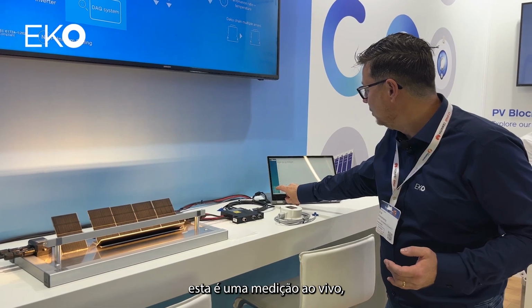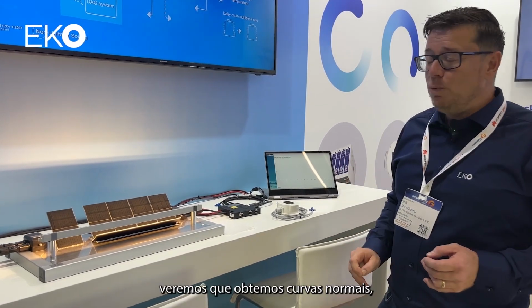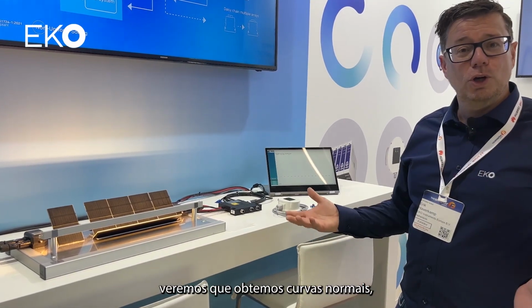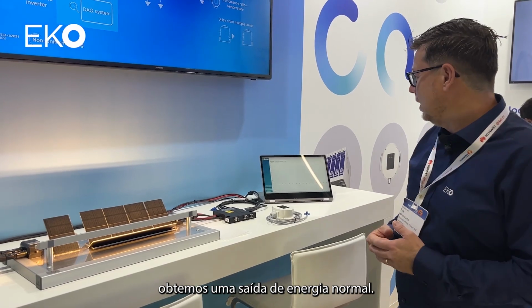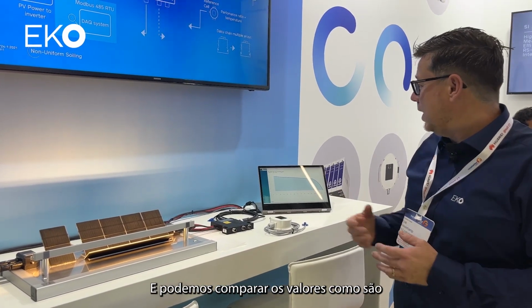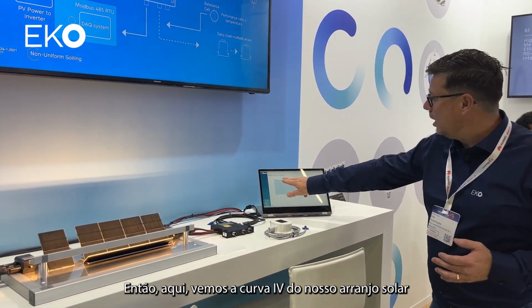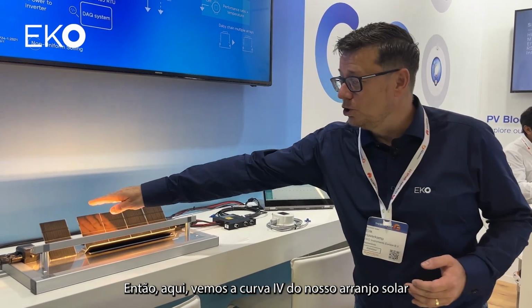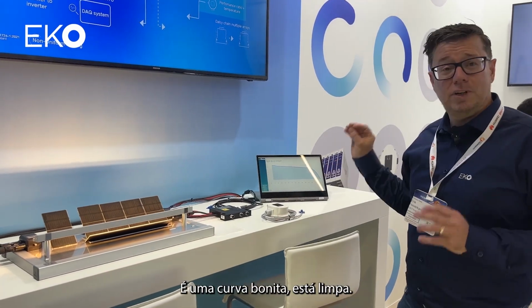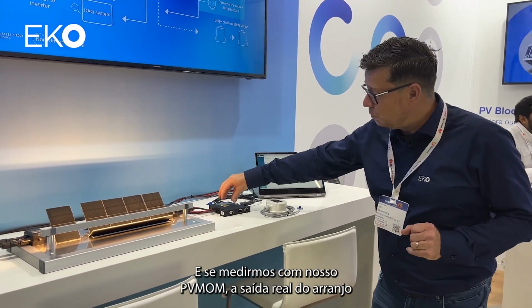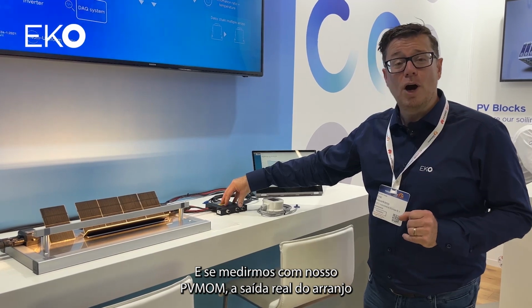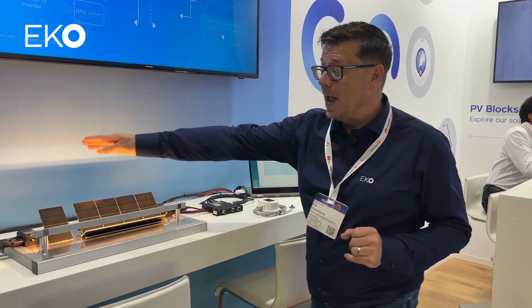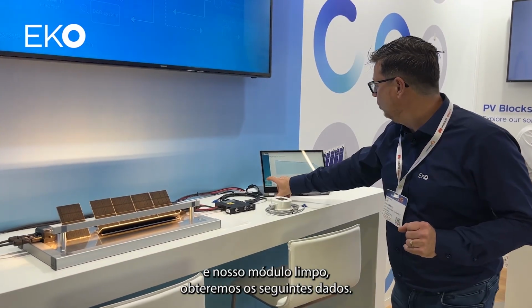If we have both systems clean and we're trying to measure the performance, this is a live measurement, then we will see that we get normal curves, we get normal power output, and we can compare the values as they are. So over here we see the IV curve of our solar array. It's a nice curve, it's clean, and if we measure with our PV mon the real output of the array and our clean module, we will get the following data.